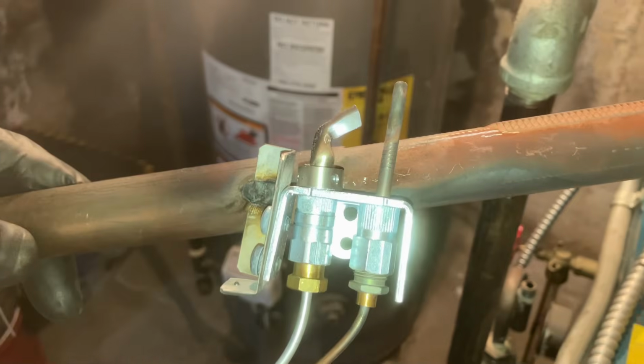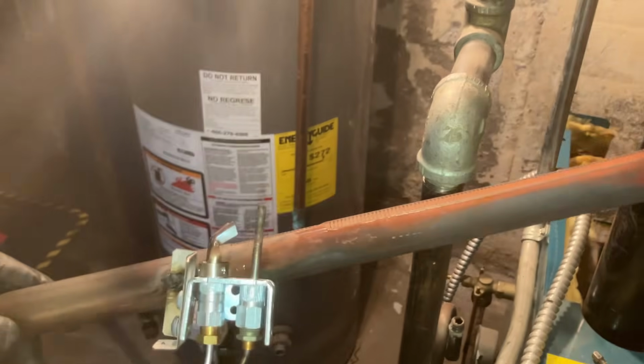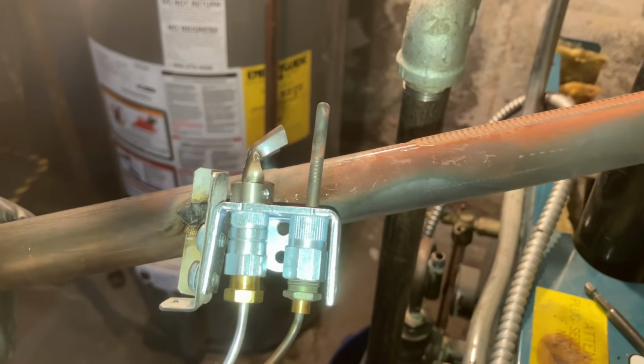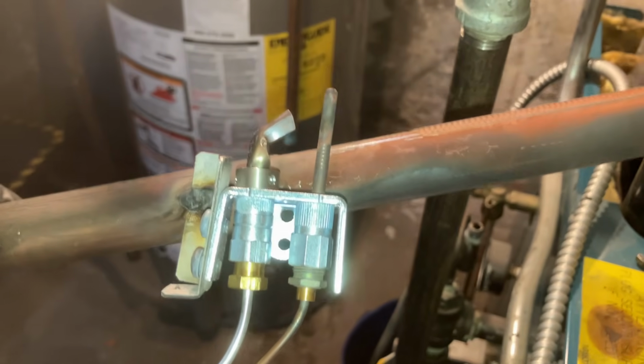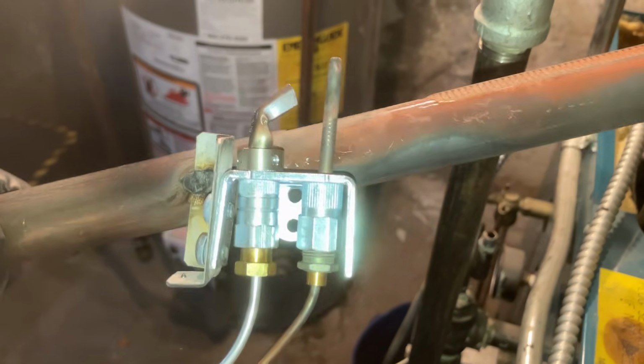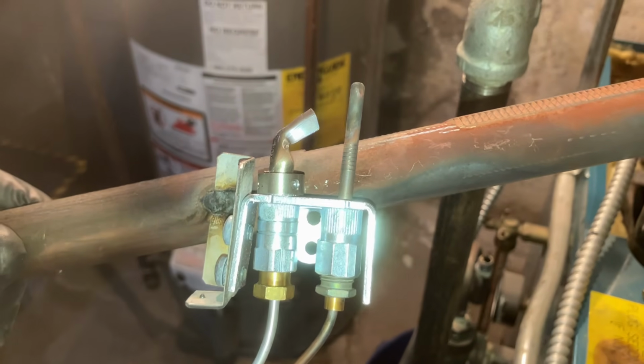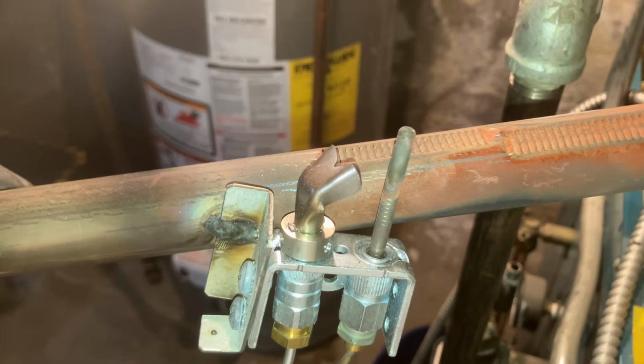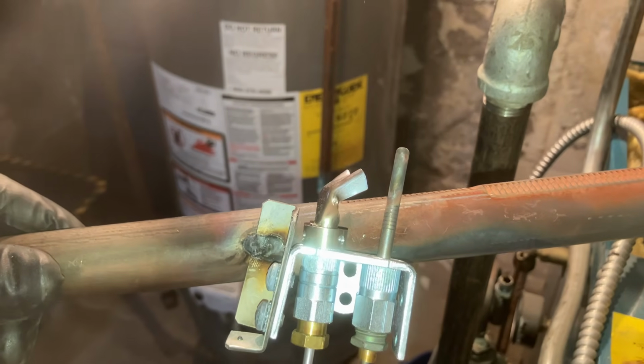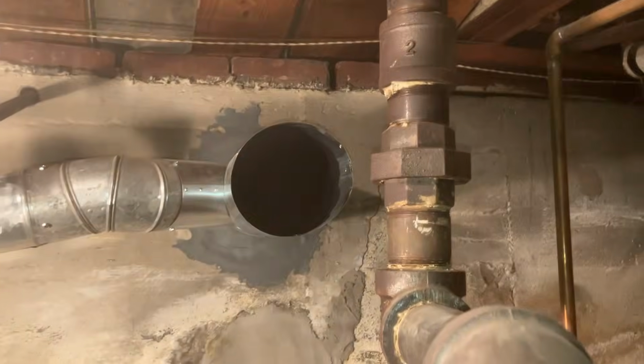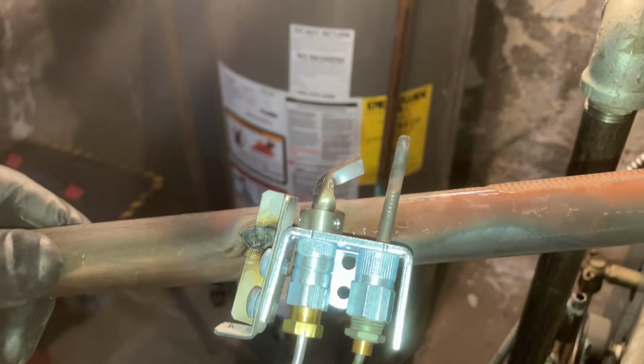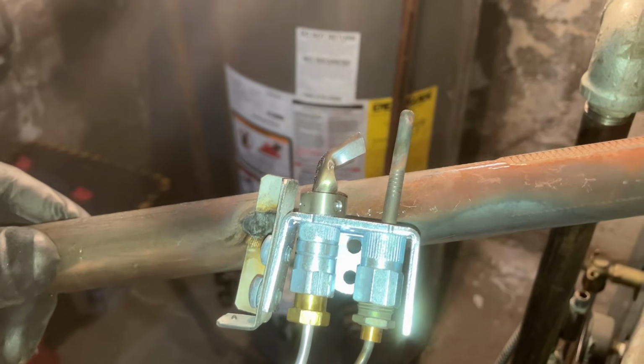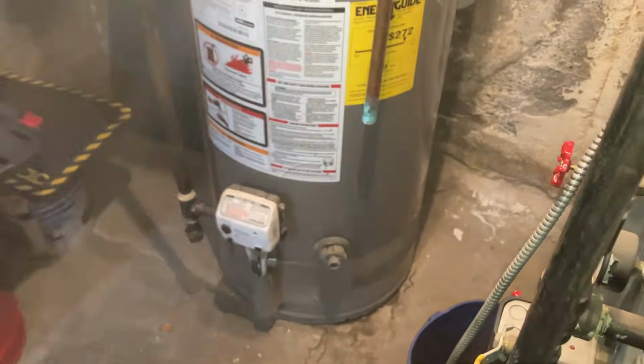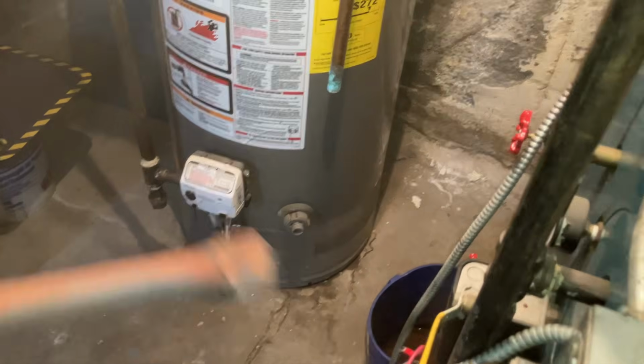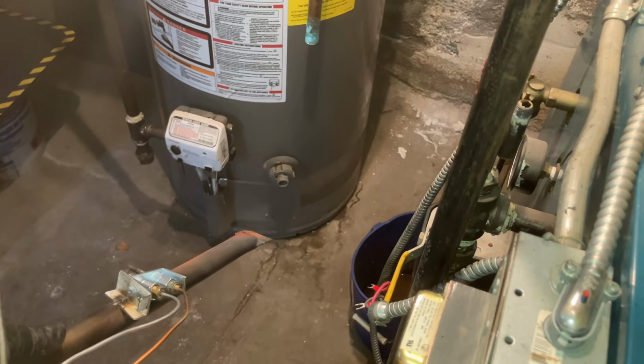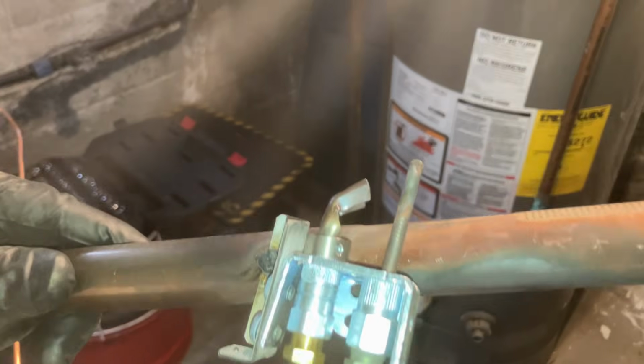So about 2 months ago, the homeowner was unable to light the pilot because they have no heat, and they went to a local plumbing supply house. They sold them a new standing pilot burner, not this one, right? And the orifice for the pilot burner was never installed. So all of this was caused by no orifice. So you had a giant flame, like a flamethrower, instead of a small little blue flame like you see in the bottom of your water heater. By the way, that drip leg is not to code. It needs to be a max of 6 inches off the floor, minimum of 1 pipe diameter off the floor.